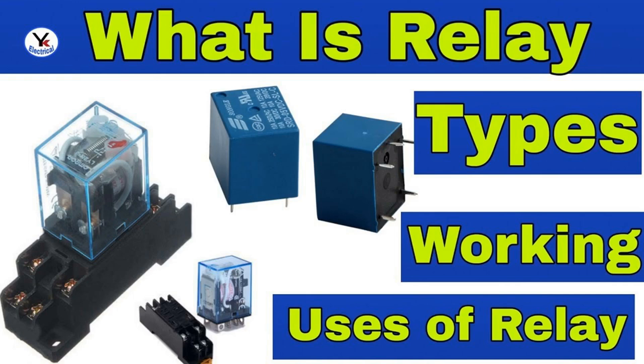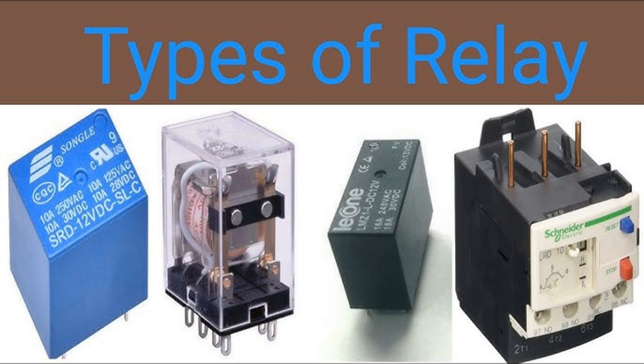Disadvantages: Slow response time — compared to other protection devices like electronic relays, thermal relays may have a slower response to sudden overloads. Temperature sensitivity — they may be affected by ambient temperature conditions, which can influence their operation. Limited sensitivity — thermal relays may not detect short-duration overloads effectively, potentially allowing damage to occur. Applications: Motor protection — commonly used in electric motors to prevent damage from overcurrent situations. HVAC systems — employed in heating, ventilation, and air conditioning systems to protect compressors and other components.